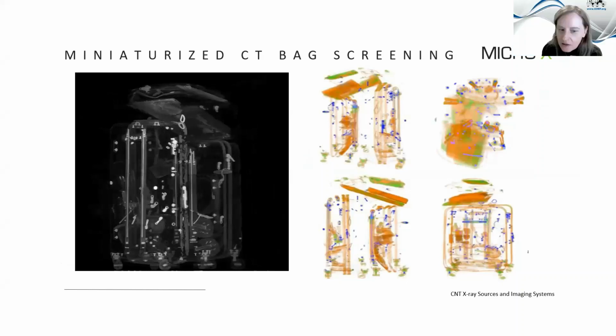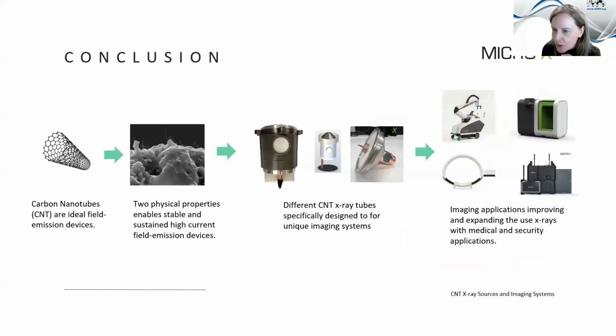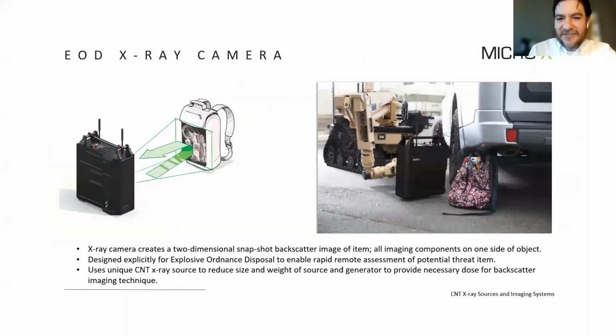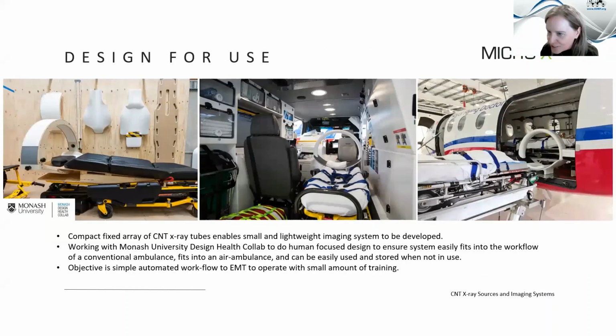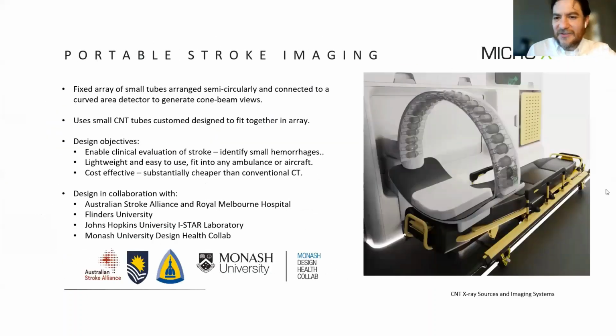Now, regarding the stroke imaging systems in ambulances or on airplanes, how do you protect the paramedics or nurses or whoever is operating the equipment? Usually we have a CT scanner inside a shielded room, and the staff operate it from the outside. There are two different ways. The first is the primary shielding is included in the individual tubes in the same way that we do with the mobile one. And so what that means is that all the primary beam is well shielded to only impact the detector.